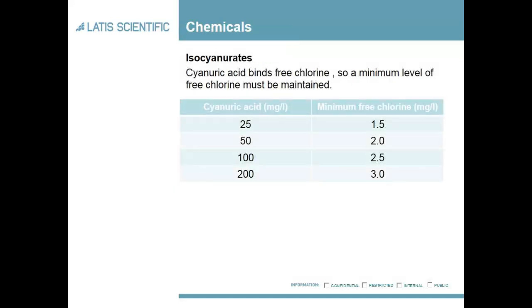The only problem with isocyanurates is that cyanuric acid binds up the free chlorine, so you need to have a minimum reserve level. As you can see from the table, based on the level of cyanuric acid you then have a corresponding minimum free chlorine level. This is usually put in via erosion feeders, as opposed to other methods, to control the level of cyanuric acid.